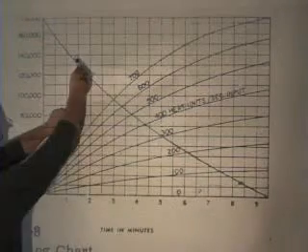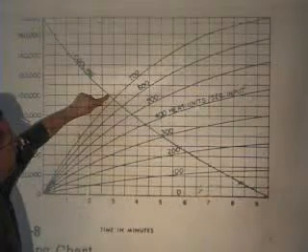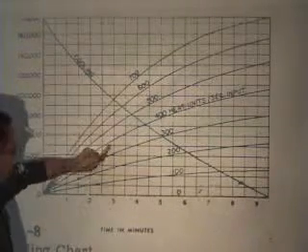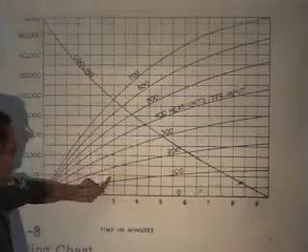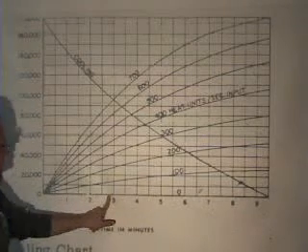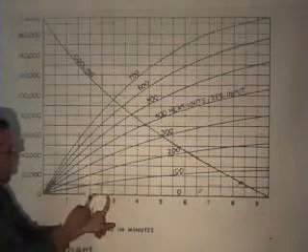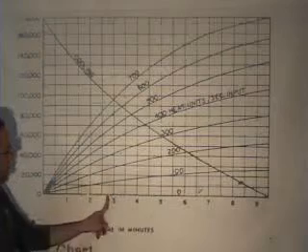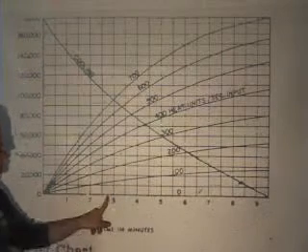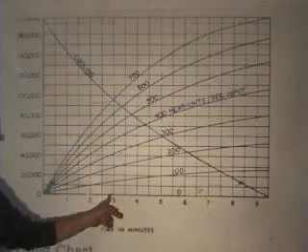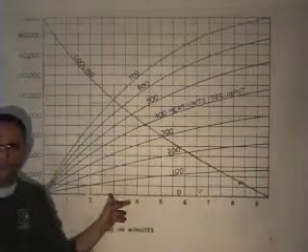For example, 100,000 heat units — you follow the line over until it hits this curved cooling line. Then you go straight down and see what time that is. Here's two minutes, here's three. This is two and a half, so it's in between two and a half and three, which means it would be about 2.75 minutes.